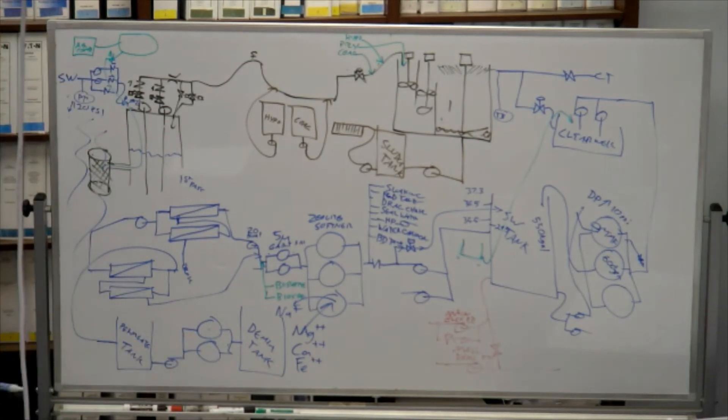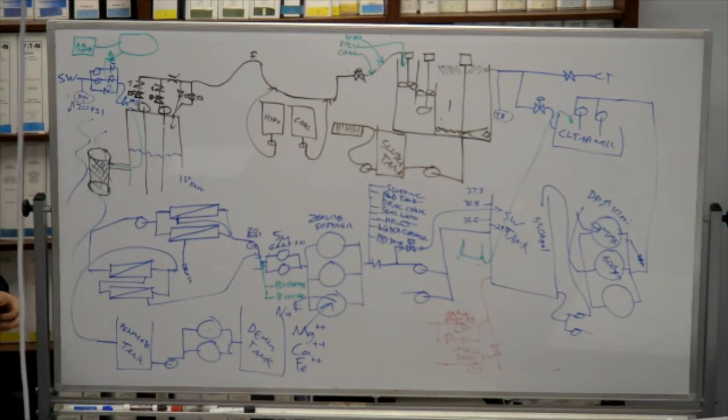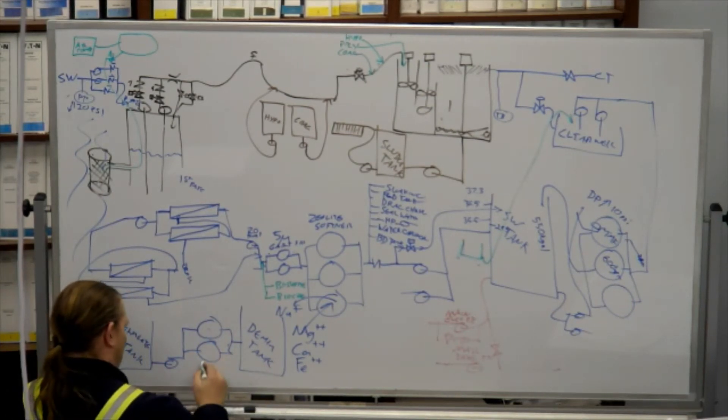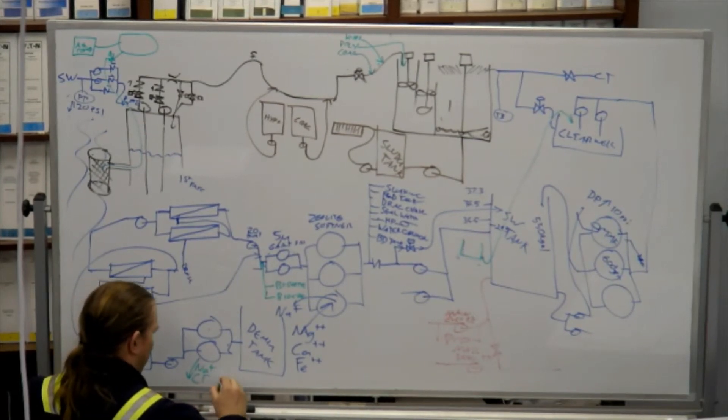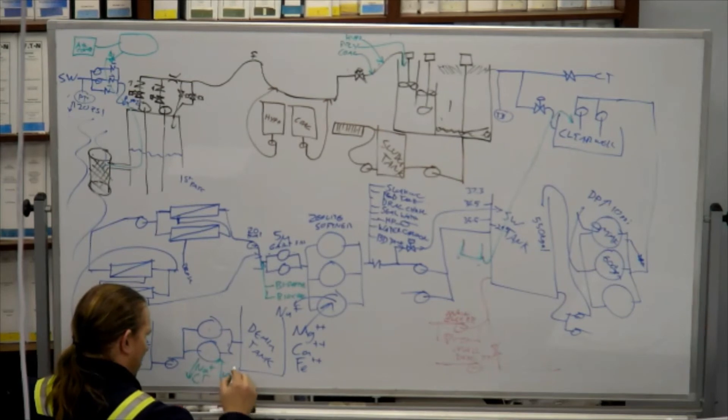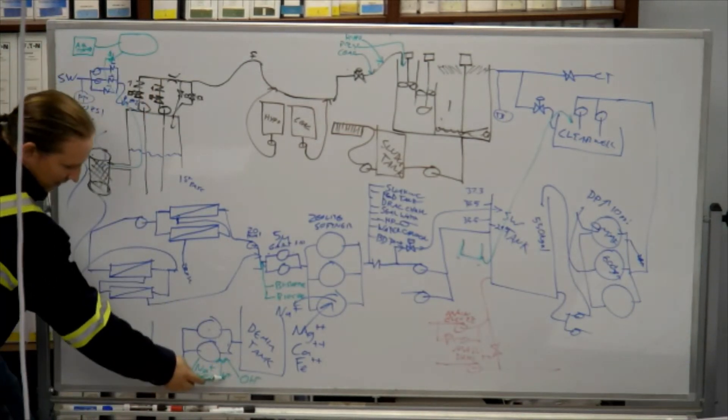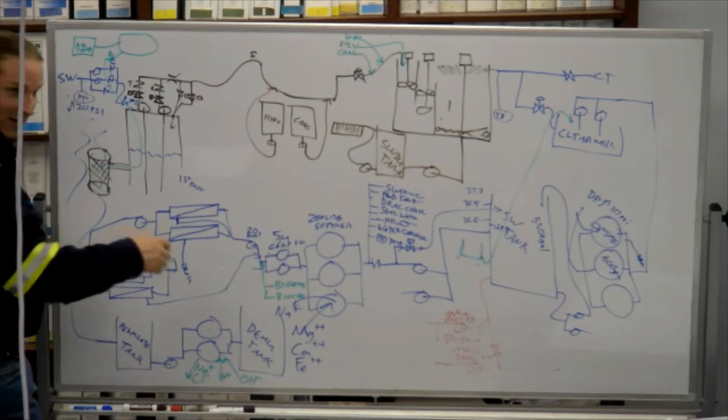Mixed beds. How do they work? What do they do? Yes, they're the same. Kind of like the polishers. They look just like the polishers. Got a thing to add besides that? They're working like the polishers. They're taking away something and adding something to it. Right. Yes. Ion exchange. So we are taking out sodium and chloride and we are putting in hydronium and hydroxide. And the fancy part here is that the H plus for the hydronium and the OH negative for the hydroxide, those come together and they make H2O. So the stuff that you're putting in is becoming water.